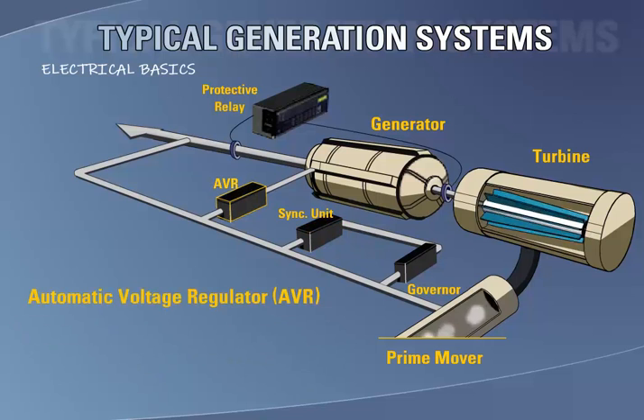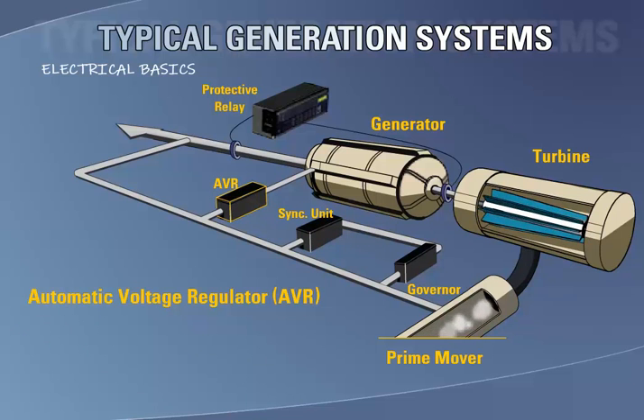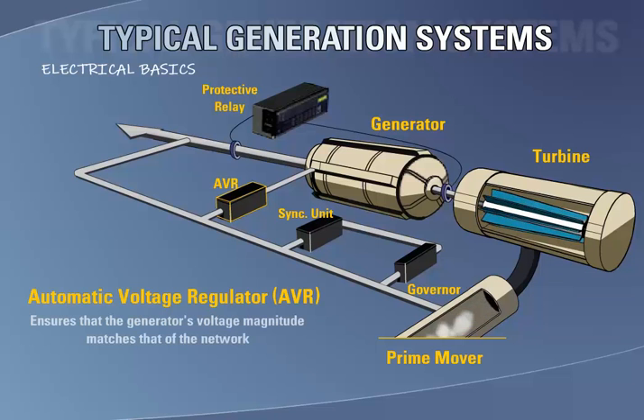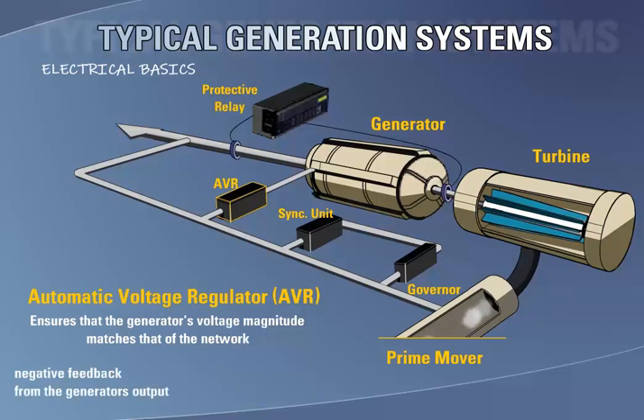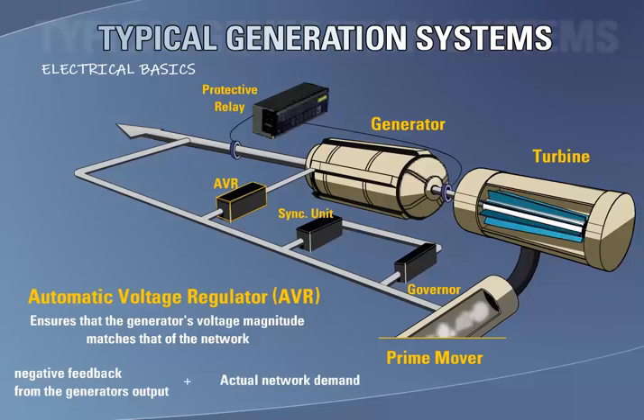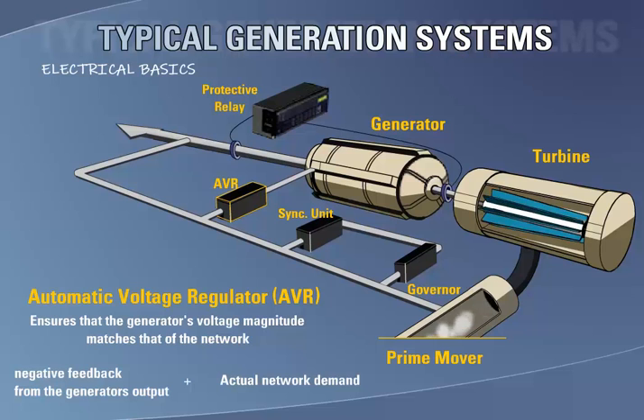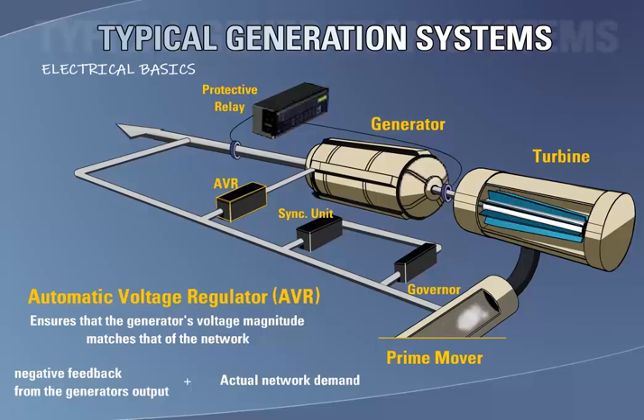The automatic voltage regulator is also an essential component in matching the power being generated to the power demanded by the network. The AVR ensures that the generator's voltage magnitude matches that of the network. It does this by summing the negative feedback from the generator's output voltage with that of the network. The error signal is fed to the generator field current regulator, which increases or decreases the field strength so that the generator voltage magnitude matches that of the network.